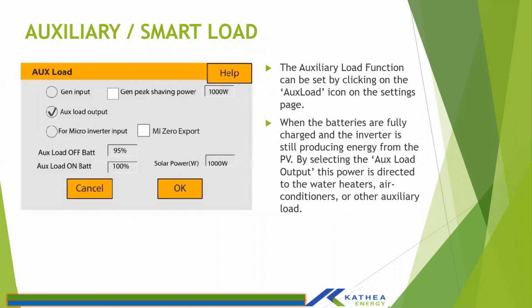And then when you are using the auxiliary port, you can use it as a smart load port. In cases where you have an off-grid system, in most instances, when you are running off-grid, all your loads are catered for. It's in the afternoon, 12 o'clock, all your loads have been catered for. The battery is now at 100%, and the PV still has surplus.